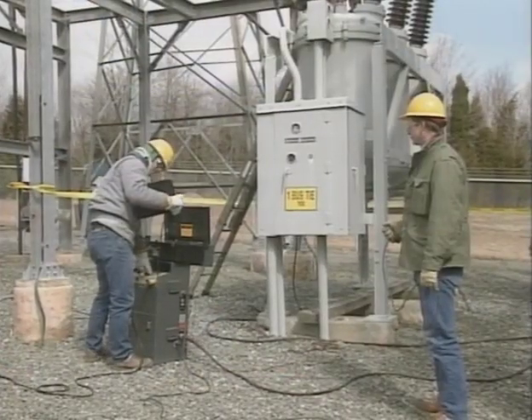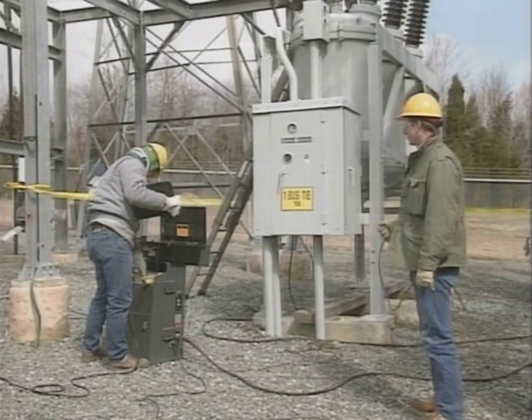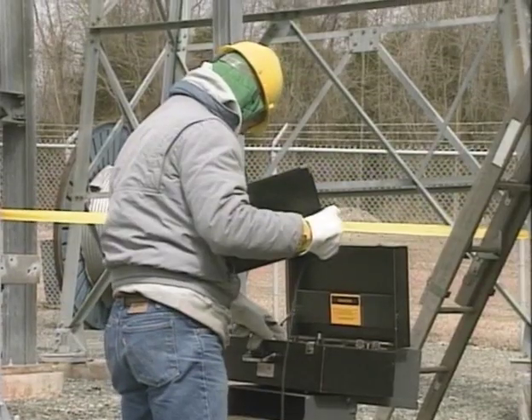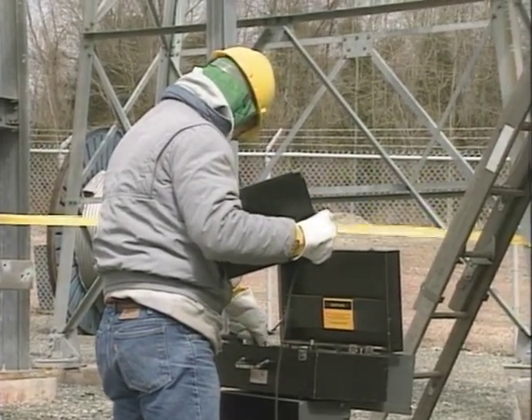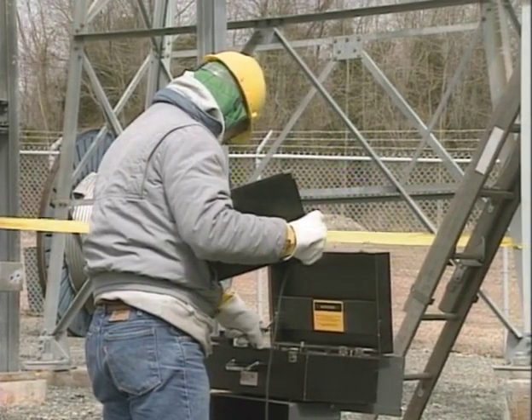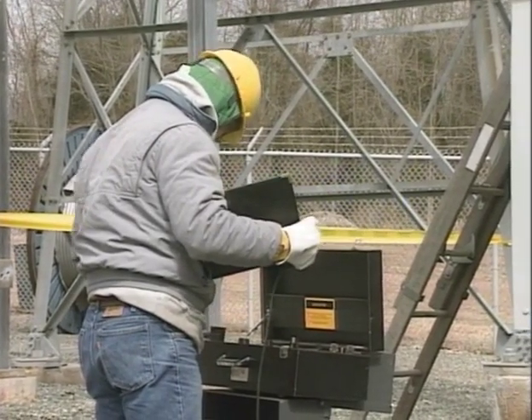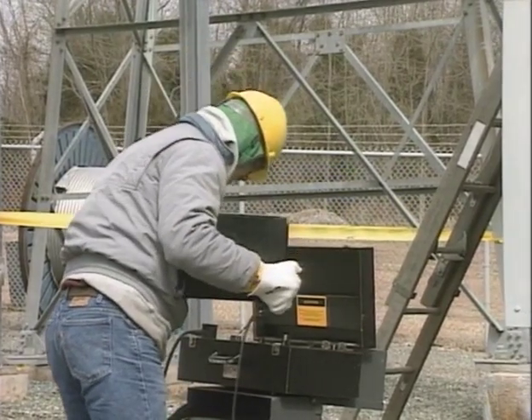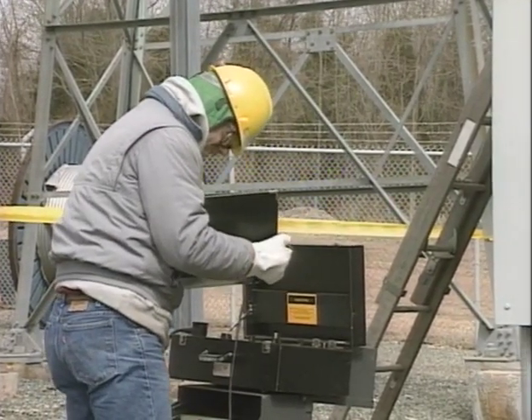As with the post-installation inspection, proof tests should be thoroughly documented. To provide meaningful comparisons with future tests, it's important to document actual measured test values rather than just noting if the test results were within prescribed tolerances.